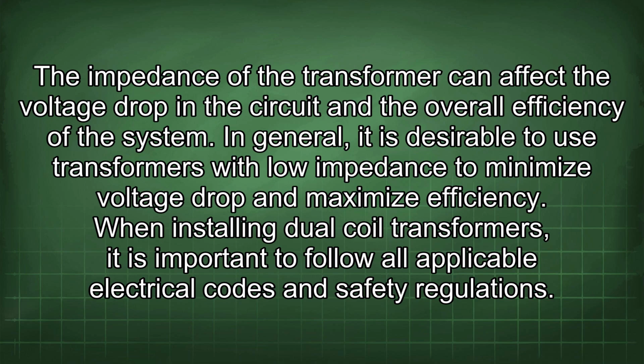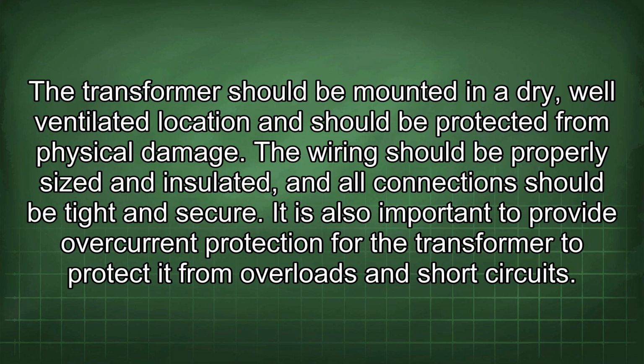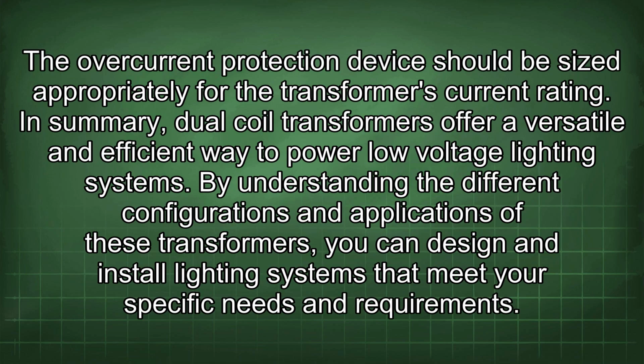When installing dual-coil transformers, it is important to follow all applicable electrical codes and safety regulations. The transformer should be mounted in a dry, well-ventilated location and should be protected from physical damage. The wiring should be properly sized and insulated, and all connections should be tight and secure. It is also important to provide overcurrent protection for the transformer to protect it from overloads and short circuits. The overcurrent protection device should be sized appropriately for the transformer's current rating.